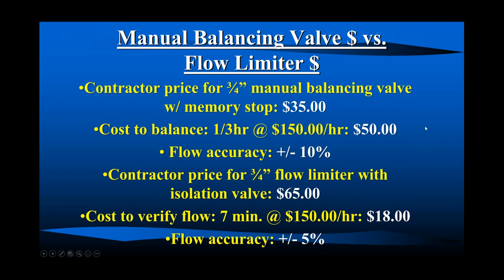And the big deal in New York City for many, many decades is this, the initial cost difference. 35 versus 65, and usually that spells, we're not using these, they're too expensive. So let's talk about that now. And that is why manual balance valves run the show in New York City. But it may be time to consider some other things because all these new systems are going to be much more flow sensitive than the previous systems we've designed. So let's talk about this because this is a big deal.